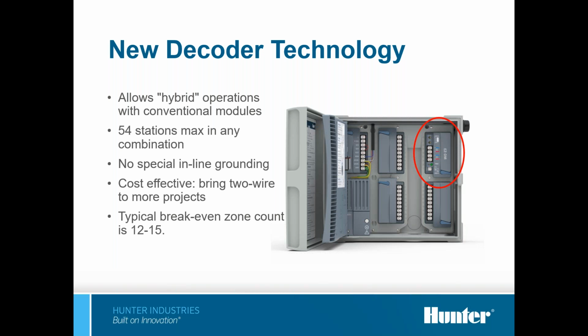With the EZ decoder system, that module plugs in, and you're also allowed to have hybrid technology. You can have some conventional wires along with the EZ decoder. When the EZ decoder is in there, it will automatically recognize what slot it's in. This one has 3 other modules, so your first stations will be conventional, and your decoder will start after that. So it would start at 25. You have 54 stations max in any combination. No special inline grounding. It's cost effective.